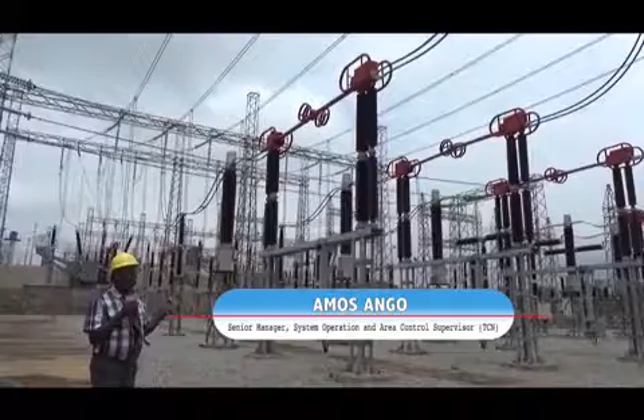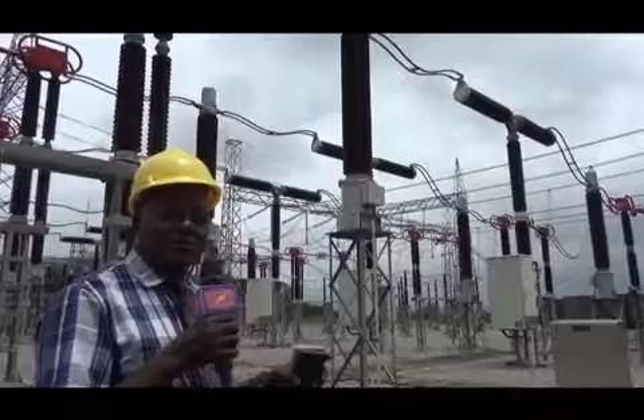These ones, as you see, drop this voltage to a usable voltage, and it is this equipment that is giving us readings in the control room. When we get to the control room, you will see the meters. Without these VTs and CTs, we can't have reading in the control room. The use is that we monitor the voltage that is coming in first, because if we have a high voltage, it has its own effect on our equipment too.